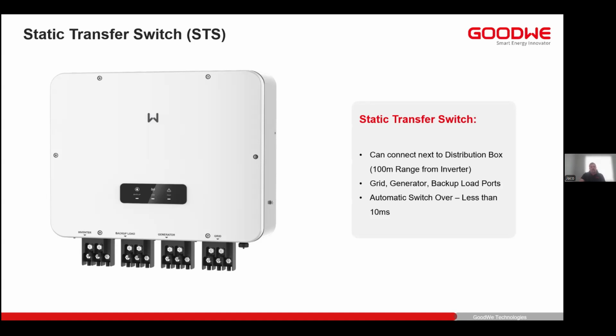The STS also has a bypass capacity of 200 amps or 138 kilowatt, which means that in many cases, there will be no need for a separate DB or a dedicated backup DB. The entire load can be added to the backup output port. And then once the grid falls away, or there's not enough PV power to carry the loads with the battery, the additional loads or the high loads can be switched off with a contactor.